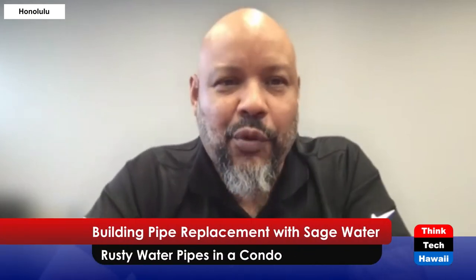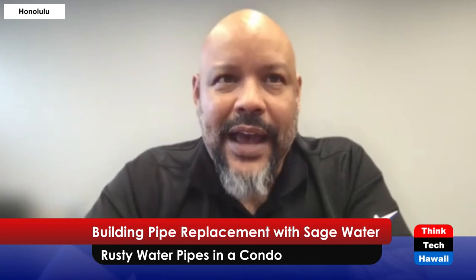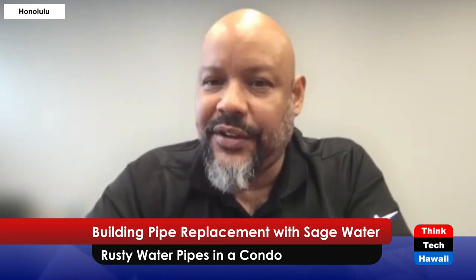So the first step is to educate yourself on what your building is actually having issues with. Is it just the waste? Some buildings it could be the supply. They're getting a lot of leaks on the supply, and maybe it's because the angle stops are starting to leak, or the supply lines are starting to leak, or they haven't been changed out in forever. People hire a plumber to come out and he tweaks it one way and it's never been moved that way. Now all of a sudden it's cracked and he doesn't notice it. He leaves, and then next thing you know, it starts leaking.